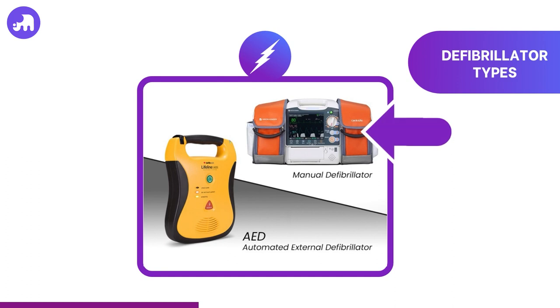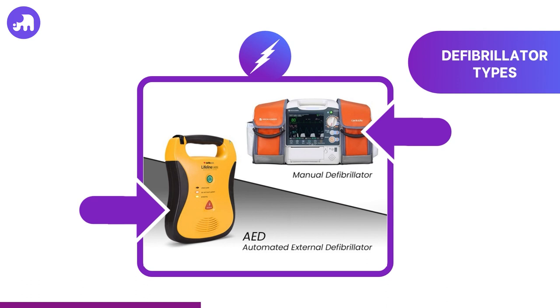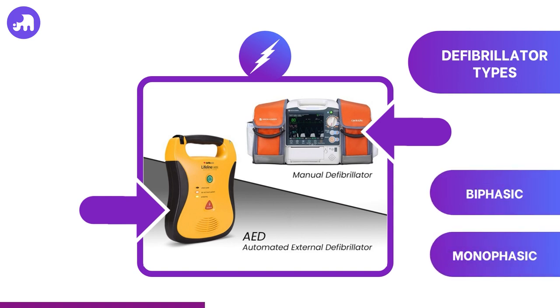There are fundamentally two main types of defibrillators. First, manual defibrillators, used by trained healthcare professionals who can discern abnormal heart rhythms and decide on the requisite response. Second, automated external defibrillators, or shock advisory defibrillators, designed to autonomously diagnose the cardiac rhythm and conclude if a shock is necessary, guiding the rescuer throughout. Depending on the device type, these will administer shocks utilising one of two electrical waveforms — biphasic or monophasic — so we need to better understand what the difference between these waveforms represents.